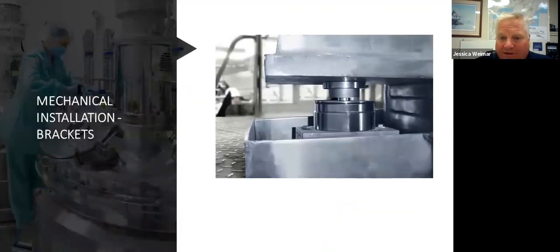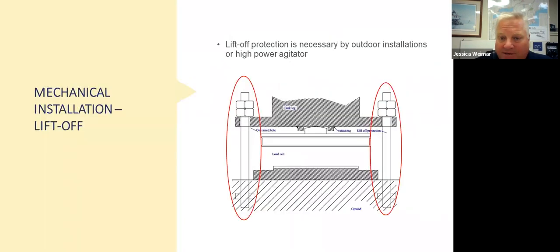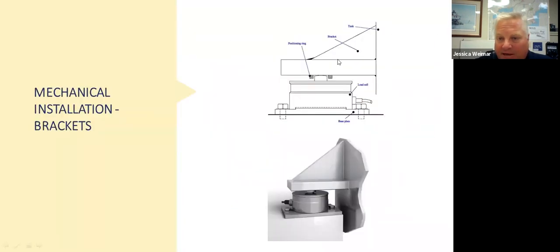One thing you do have to think about, though, is that you've given enough clearance between the button and the ring so that the load cell, the tank, can move thermally. What does that mean? If I've got a tank that's 10 feet in diameter and I raise the temperature 100 degrees, the tank's going to grow. The tank needs to be able to move on top of that load cell in a way that it doesn't bind up. So those are some considerations you need to think about, okay?